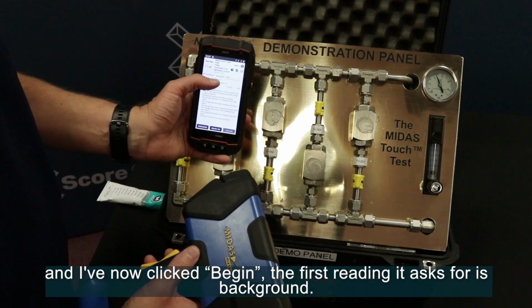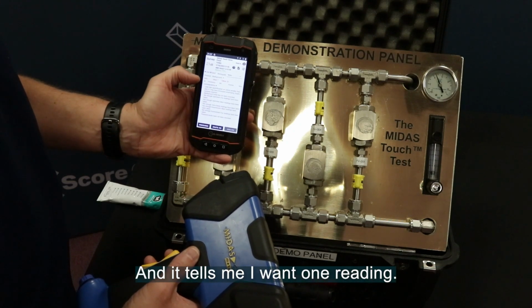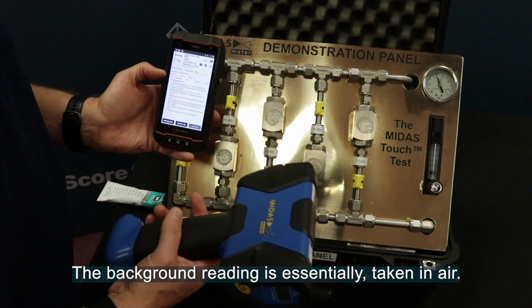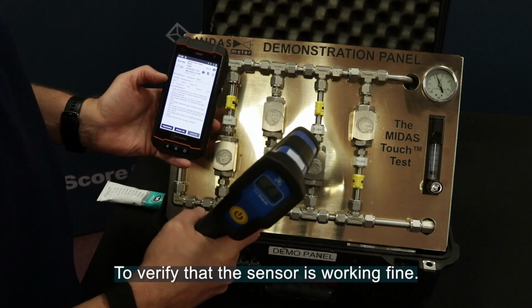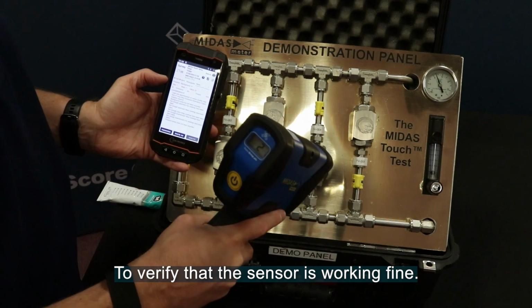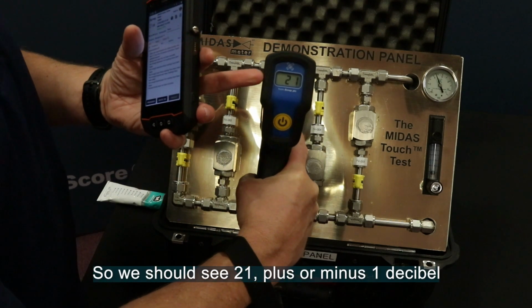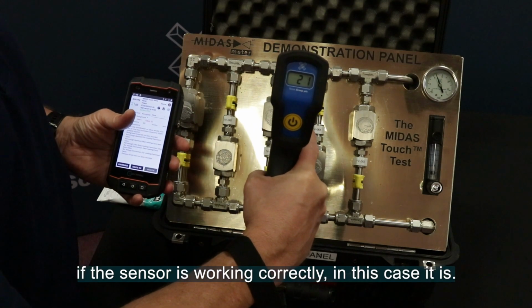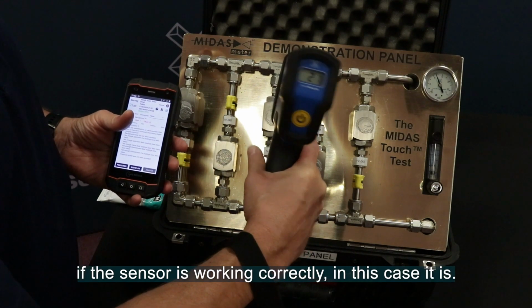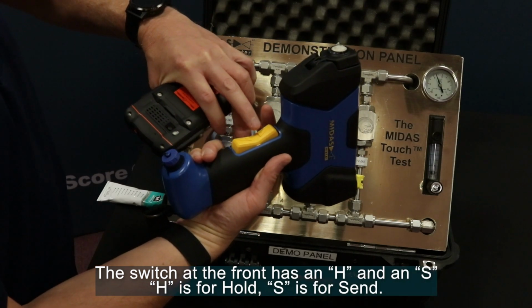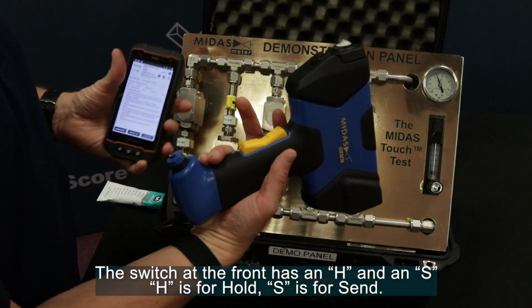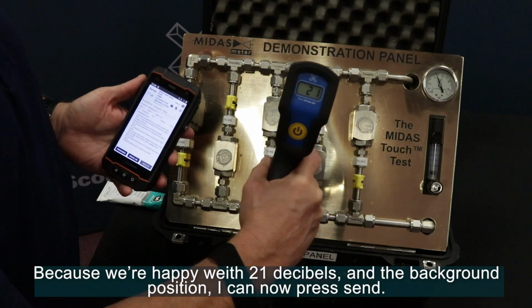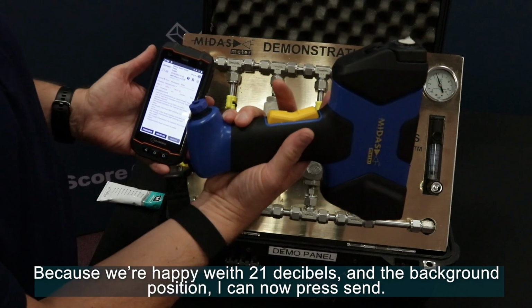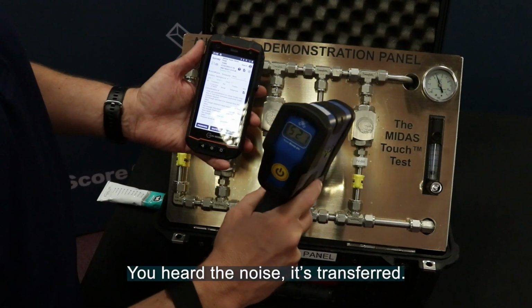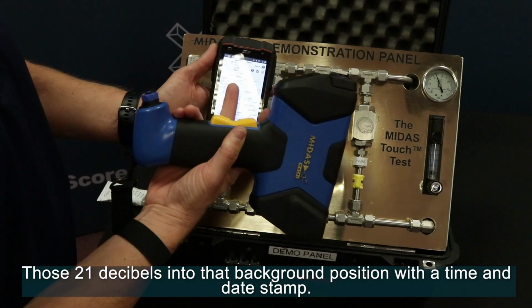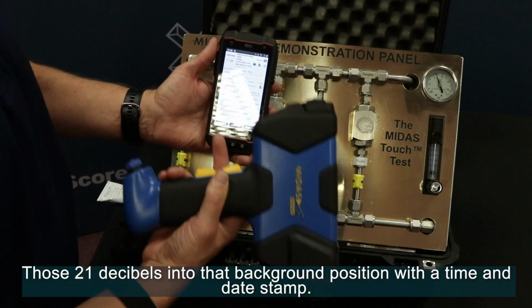The first reading it asks for is background, and it tells me I want 1 reading. The background reading is essentially taken in air to verify that the sensor is working fine. So we should see 21 plus or minus 1 decibel if the sensor is working correctly, and in this case it is. The switch at the front has an H and an S. H is for hold, S is for send. Because we're happy with 21 decibels at the background position, I can now press send. You hear the noise, it's transferred those 21 decibels into that background position with a time and date stamp.